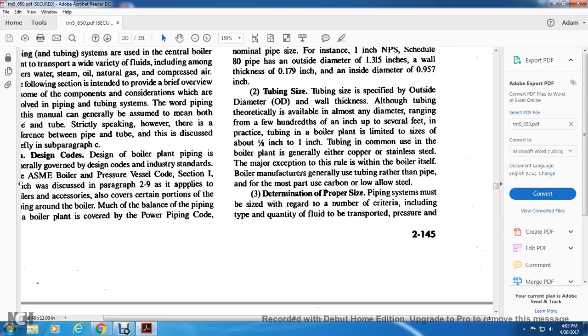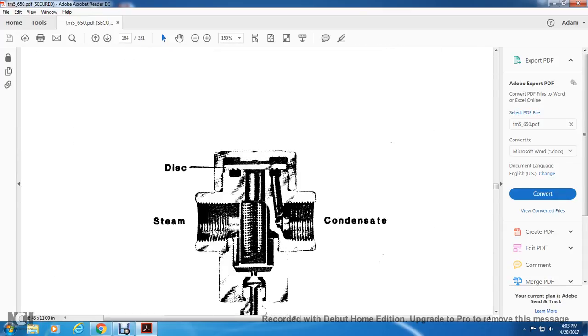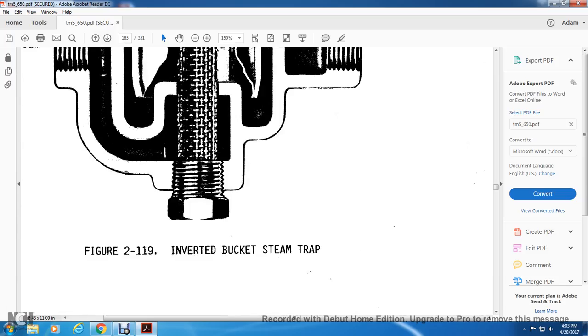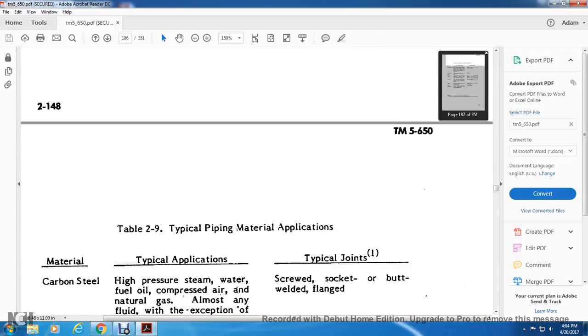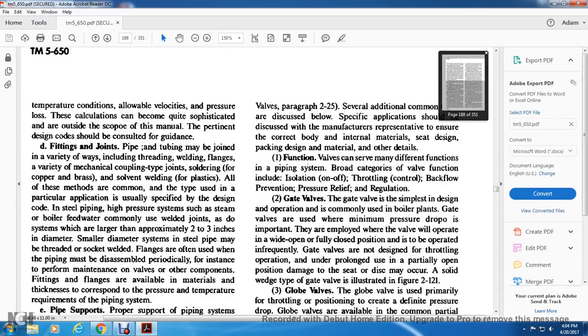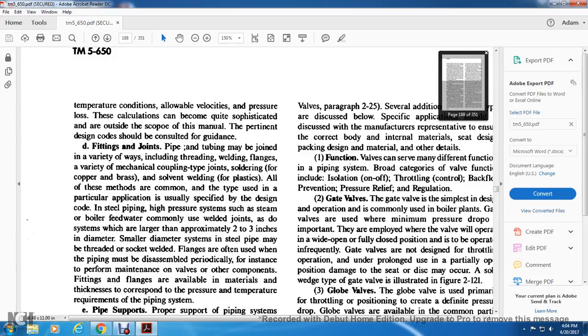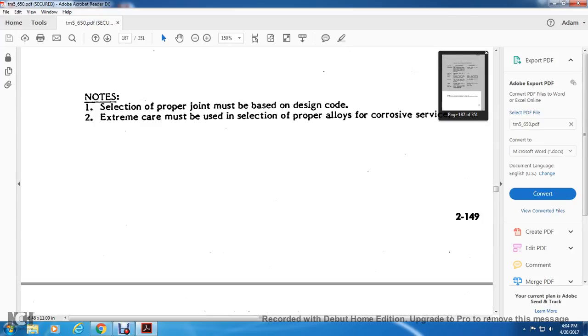For the most part, carbon or low alloy steel is used. Determining the proper size, the piping system must be sized according to a number of criteria, including the type of fluid, the quantity, and the transport pressure and temperature conditions. The velocity and pressure calculations become quite sophisticated and outside the scope of the manual. The pertinent design code should be consulted for guidance.